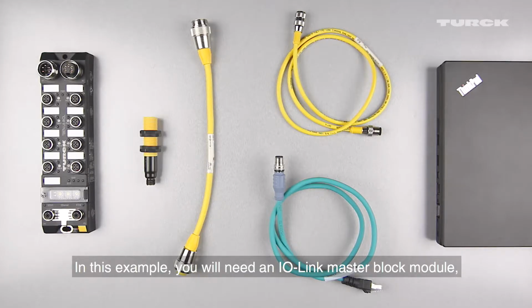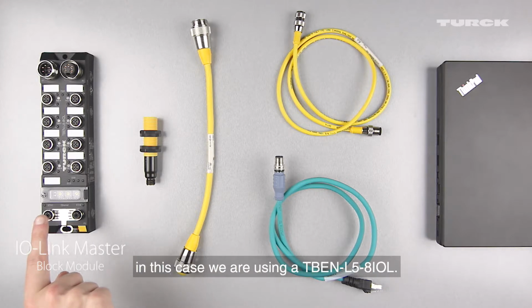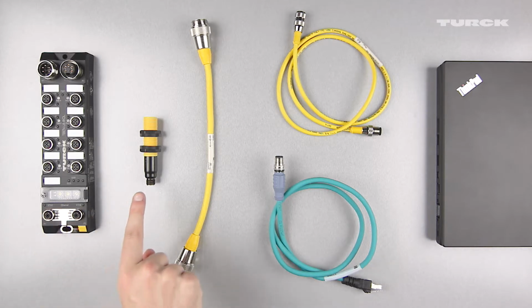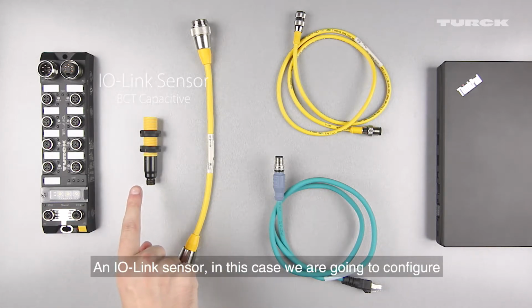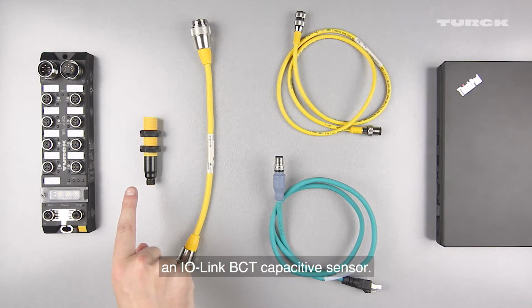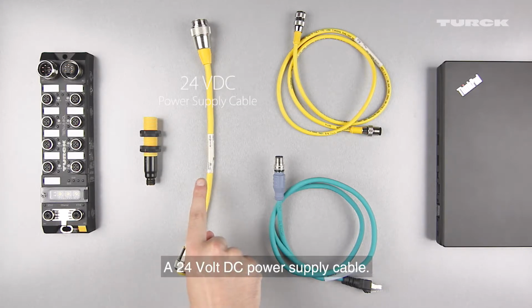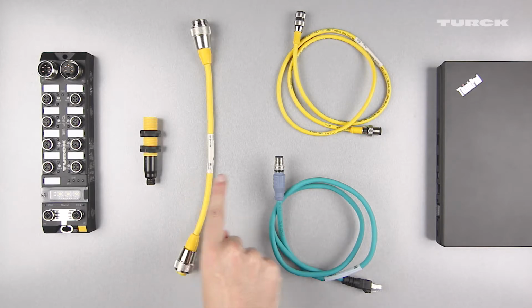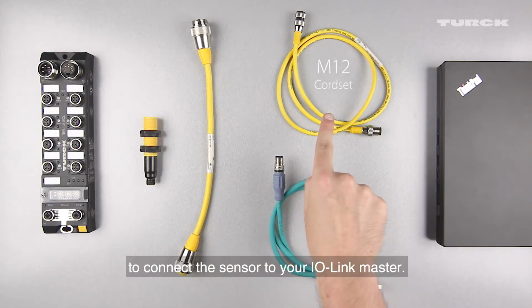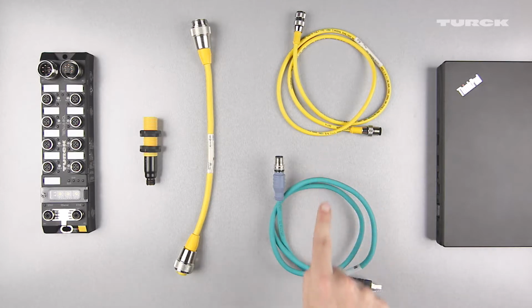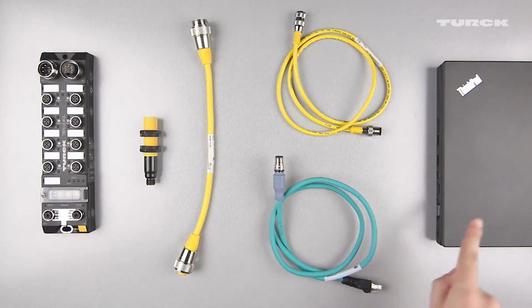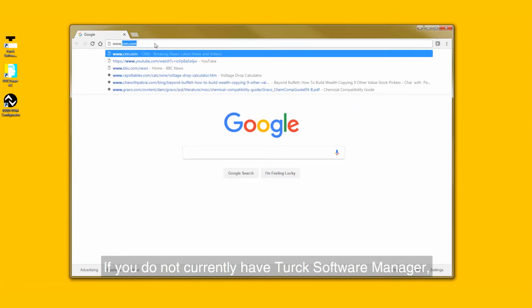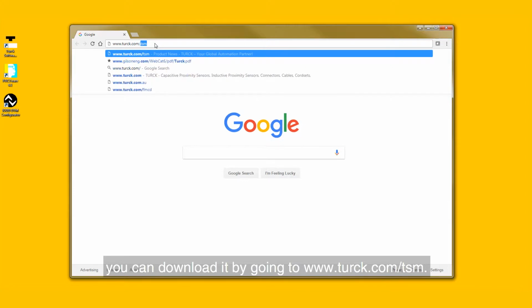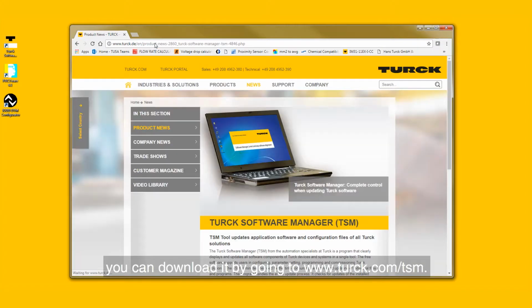In this example, you will need an IO-Link master block module. In this case, we are using a TBEN-L5-8 IOL, an IO-Link sensor. In this case, we are going to configure an IO-Link BCT capacitive sensor, a 24-volt DC power supply cable, a double-ended M12 cord set to connect the sensor to your IO-Link master, an Ethernet cord set, and a laptop or PC. If you do not currently have Turck Software Manager, you can download it by going to www.turck.com/TSM.